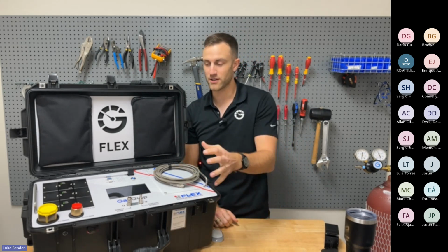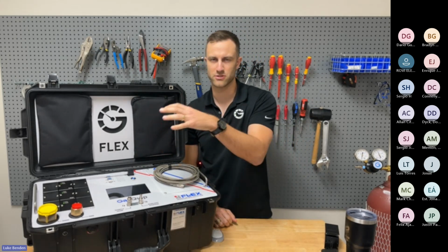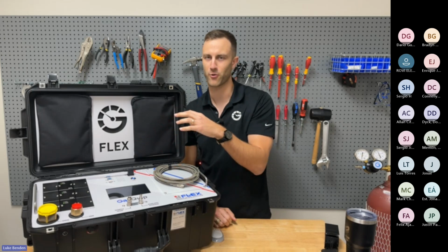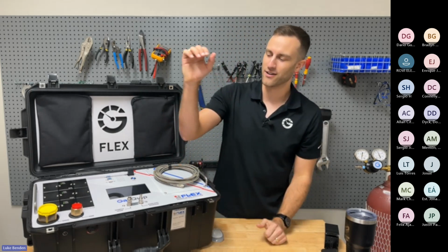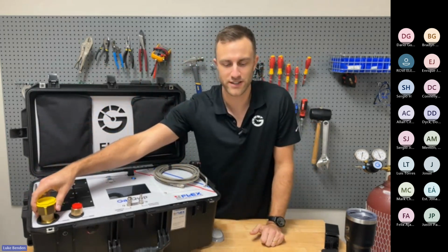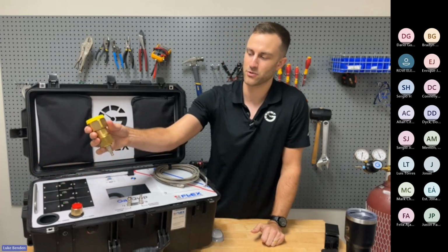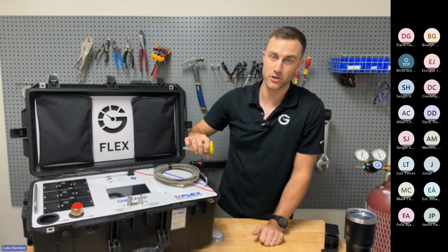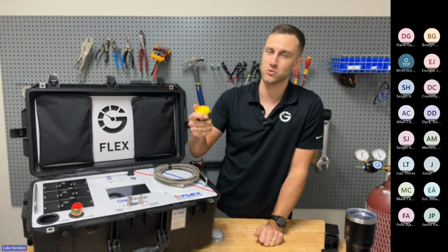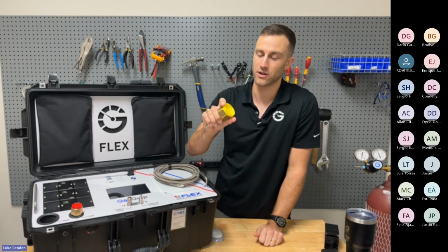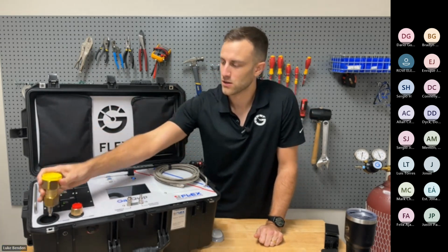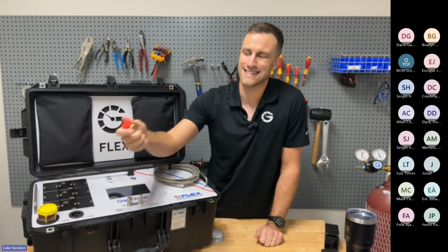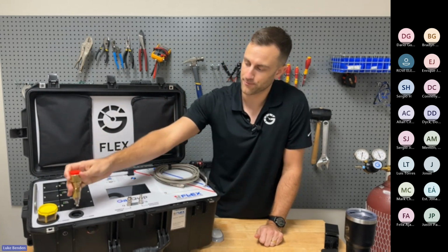So let's talk about the physical layout of the analyzer, with some terms that I'll be loosely throwing around throughout. Down here, these are adapter fittings. If you pull this out, this is an adapter fitting that'll snap onto the end of our sample hose and can connect up to a gas circuit breaker that might have a port for a DN20 or a DN8 style adapter fitting.